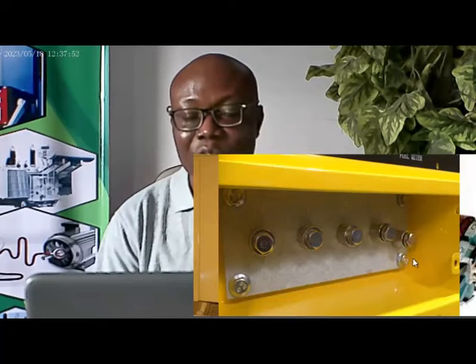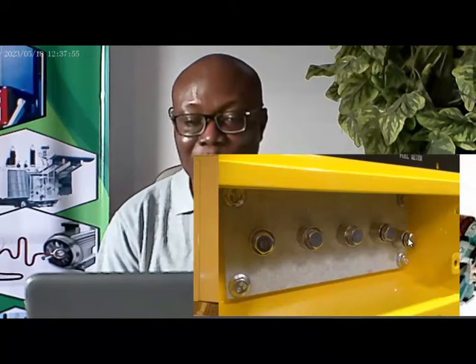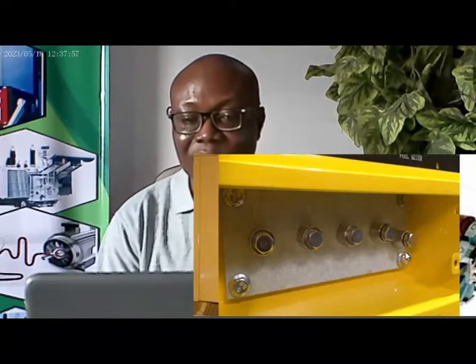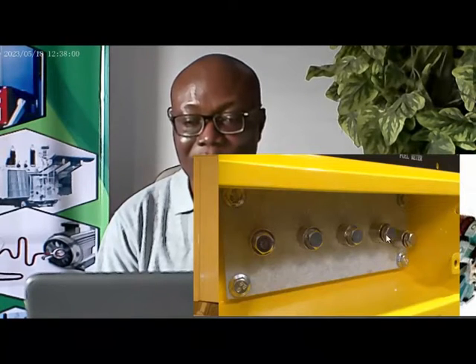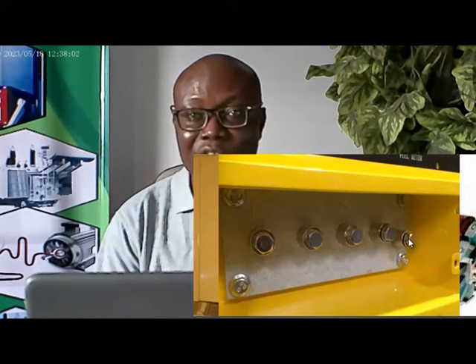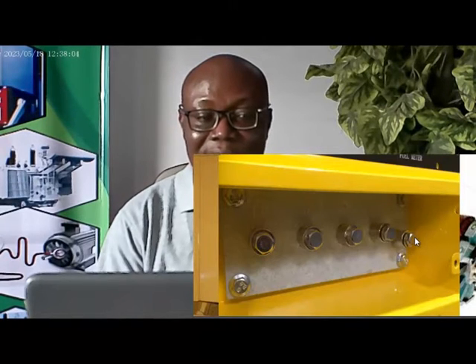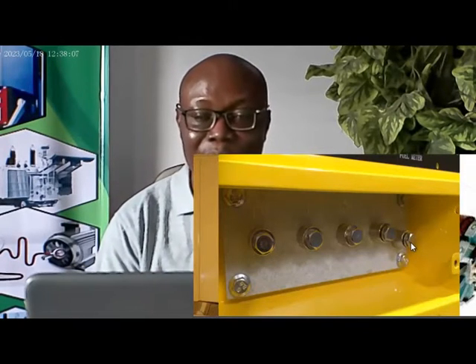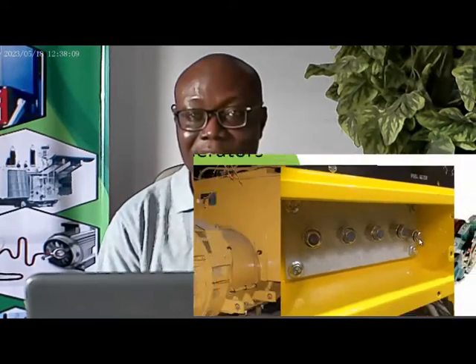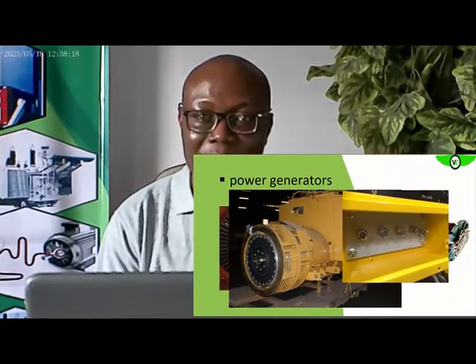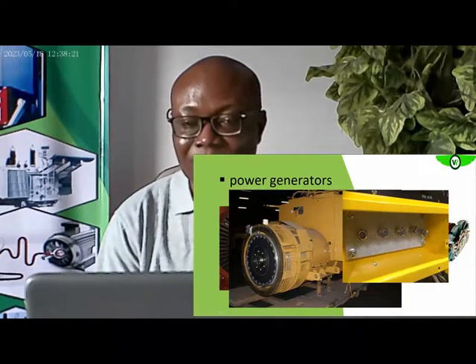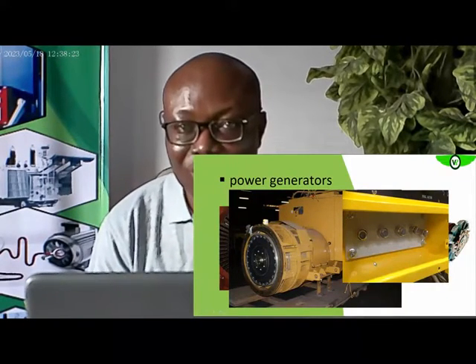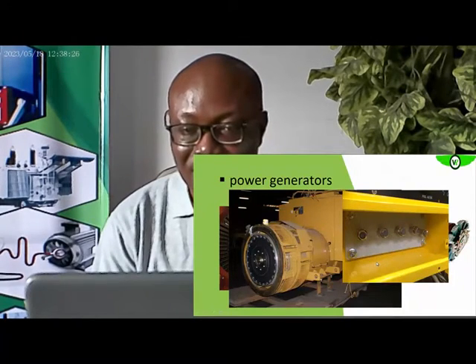Are we getting it? To do that, you can put one of the probes on any of these 4 terminals, and then the other probe on this terminal. When you inject, the insulation resistance you get is the one separating the winding from the ground. That is the insulation within the slot. If any of them is failing on any of the slots, it will cause an increase in leakage current, and you will see a drop in the insulation reading of the generator.